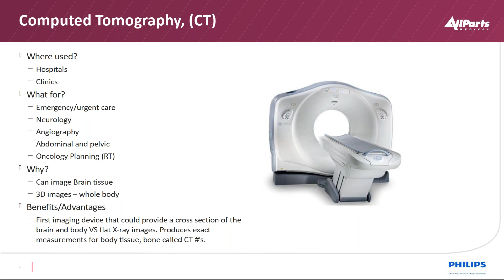One of the things that we are very concise with in a CT scanner is a scaling system. It's called the Hounsfield scaling system, but we know it nowadays as CT numbers, because obviously of computerized tomography. Essentially, they're the same. Distilled deionized water should have a CT number of 0 plus or minus scientific error, which will be about 4%. Bone will have a high positive CT number, and air will have a negative CT number, almost the full range. So this is called Hounsfield scaling, or CT numbers as we know them today.